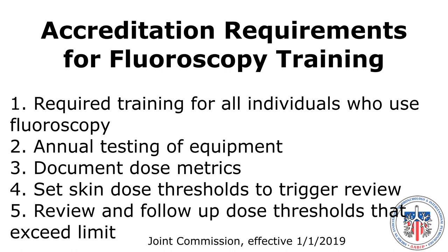Other requirements include annual testing of equipment, documentation of dose metrics, ensuring skin exposure thresholds are set, and reviewing and following up on dose thresholds that exceed this limit.